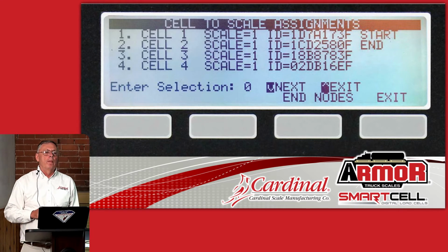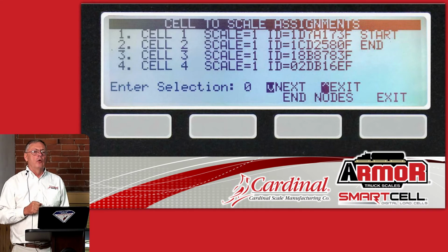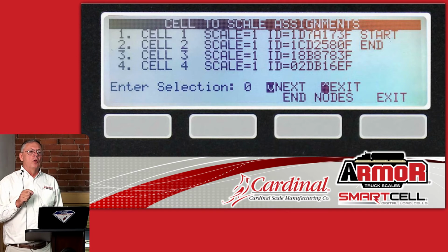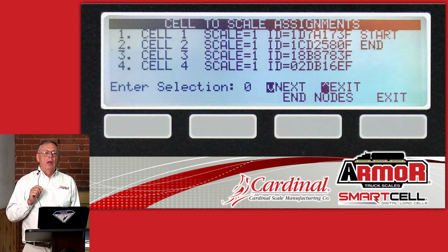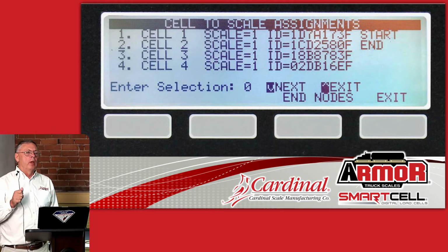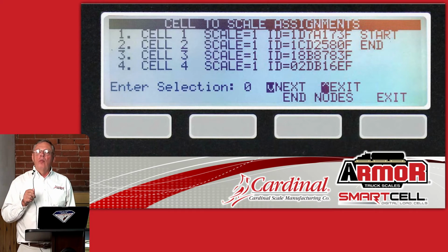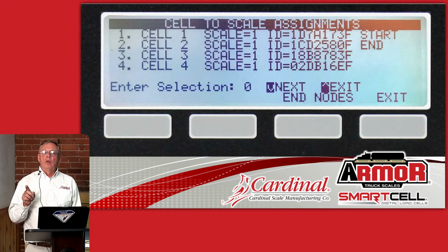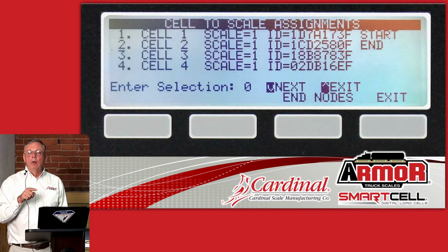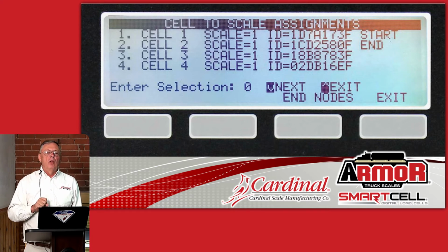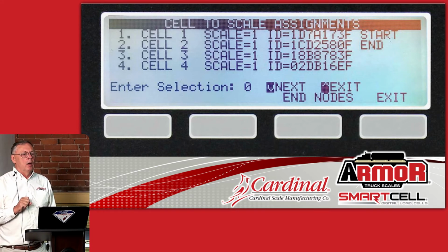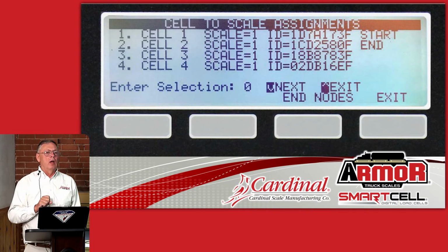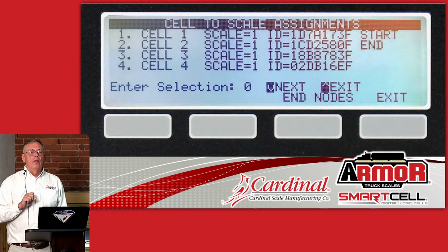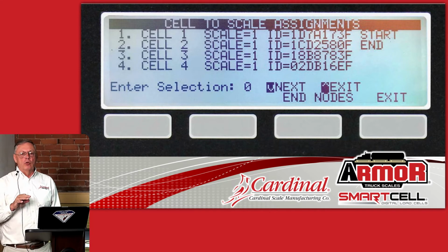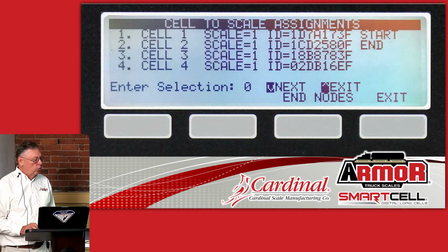In the case of a load cell failure in the field, normally we can tell which load cell is bad. And when we see a new load cell that's been put into the system, we assume that new ID number was put in the slot where the old load cell was that was bad. So you don't have to do anything to add one load cell to the system. In the event that maybe you'd taken just a terrible lightning strike right to the deck and maybe 2 or 3 load cells went out, then you'll have to go in. If multiple load cells are changed, you'll have to go in and put those serial numbers in.